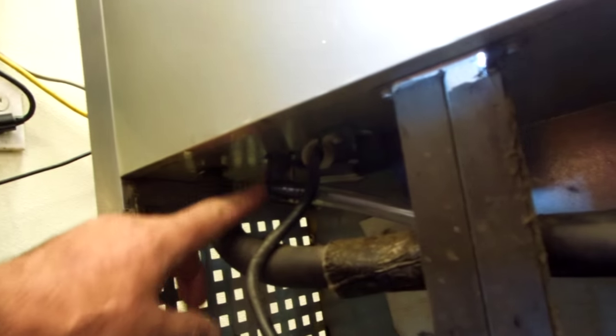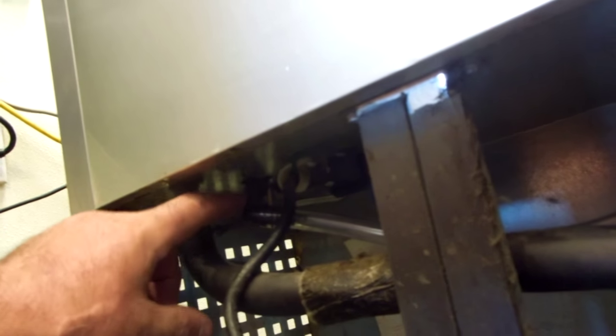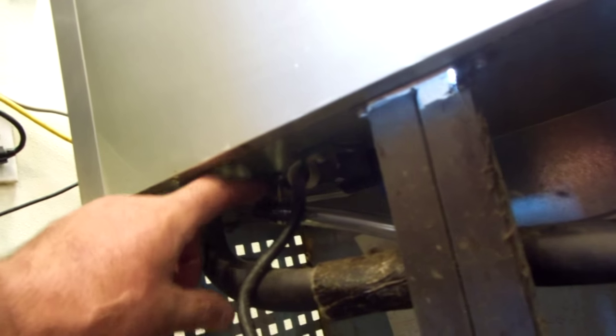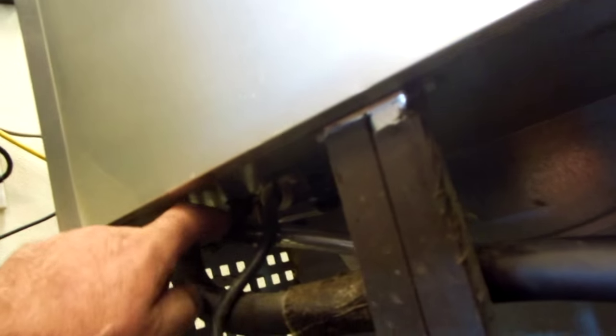You want to be careful — don't pull this one off in the case. You want to just pull the 90 out if you want to, but I wouldn't even advise it. I don't even take the 90s out. I just leave the 90 and blow it and make sure it's clear. You can break those things off where they come off. Sometimes they attach at different places. I don't recommend pulling this side out on the left. This one you can pull out, but you've got to be very gentle with it. It just slides on the plastic fitting — they're really fragile.